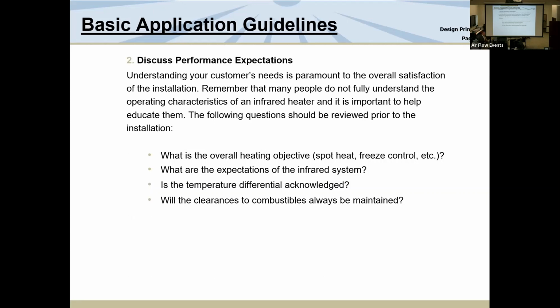And it comes down time and time again to expectations. I will tell people now when I'm driving, you saw this with the golf range: if your expectation is a 15-degree temperature rise under a 5-mile-an-hour wind, I can do it. But if your expectation is to put golfers on that golf range when it's 20 degrees and the wind's blowing, super hard, I can't do it. Your expectation on the tube heaters: if you put in one heater, you're going to have a hot end of your building and you're going to have a cold end.